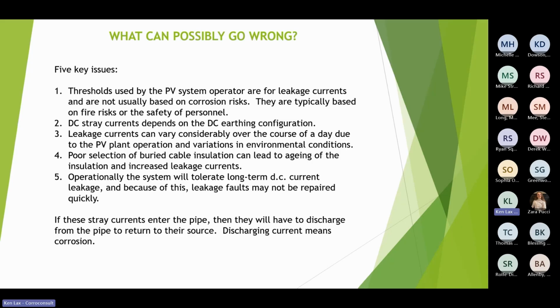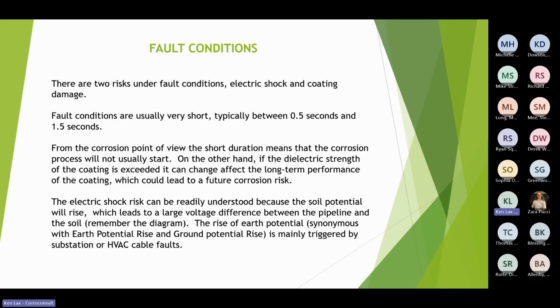deal with that risk. The stray current risks do depend very much on the configuration of the system, whether it's floating, whether it's earthed. And leakage currents can vary considerably. When it first goes into operation, it's all super. If they don't maintain the system over the years, the resistance between the panels and the earth will get lower, and so more will go on. So it's a difficult situation.